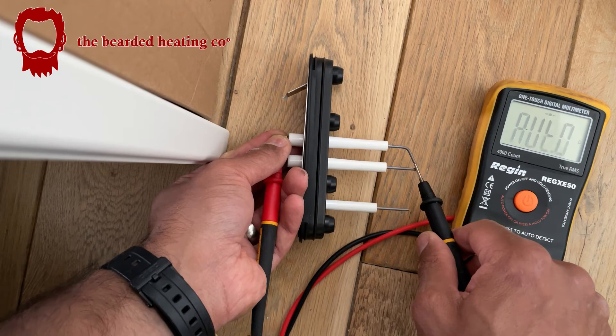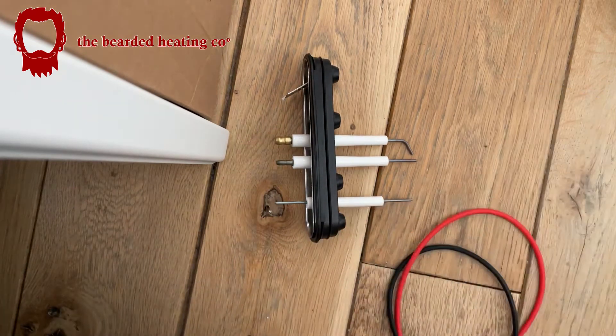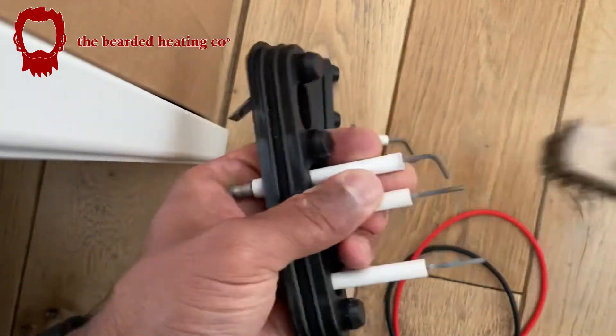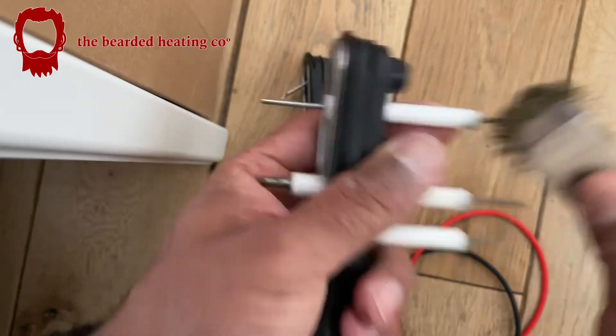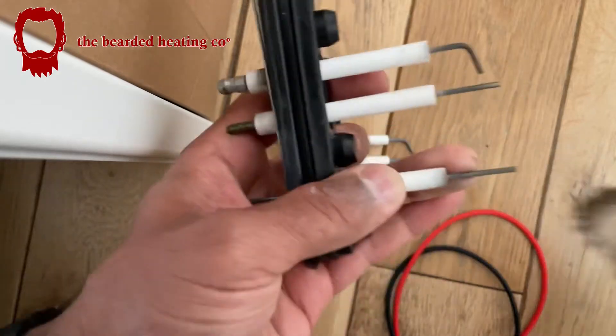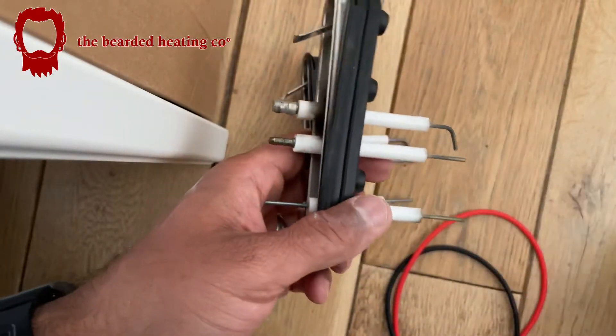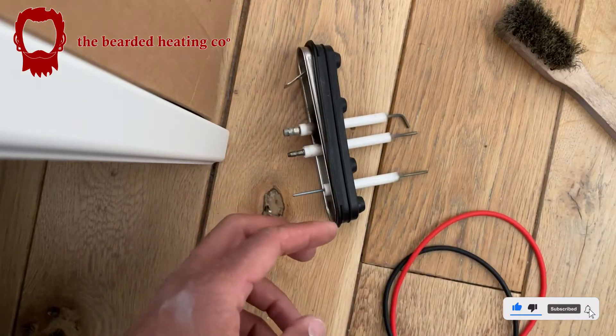Right to the tip — there you go, continuity. So that's why it's important to try to clean these. Just for test purposes, let's see if cleaning makes a difference. If I get good continuity I'll probably put the existing ones back in and ask the customer to monitor for the next few days, and come back to replace them if needed.